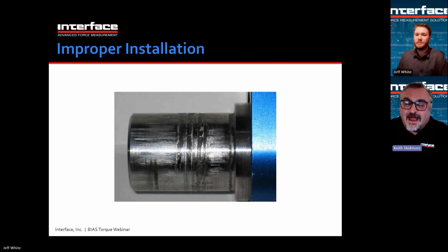You can no longer slide a coupling hub on or off without further damage. And basically it's ruined, or you could potentially machine the shaft to a smaller diameter to clean it up. But it's hard to machine a shaft that's actually installed in a torque sensor. Cutting fluid, cutting loads, those kinds of things can be quite damaging to the sensor. So usually these are scrapped at this point. Or you can rebuild it by replacing the shaft and maybe saving some of the electronics, but that's undesirable.